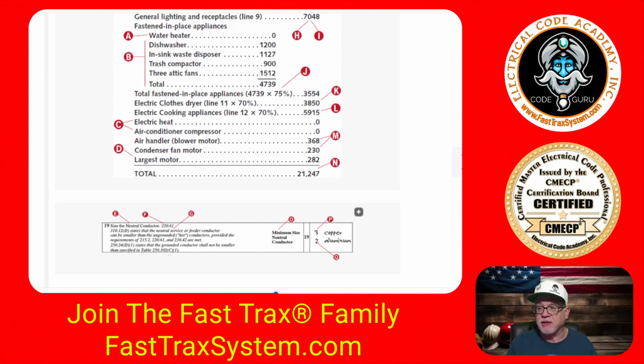That is the one that's listed in here originally as a horsepower value. That is the largest motor. So I'm going to take that 282 and I'm going to do what? I only want 25% of that. Now you might be saying, Paul, where did I get that 25%? Well, that comes from the requirements in 220.50 for the largest motor. And it sends you to 430.24, which says, look, if you've got multiple motors, take the largest one at 125% and the sum of the others.